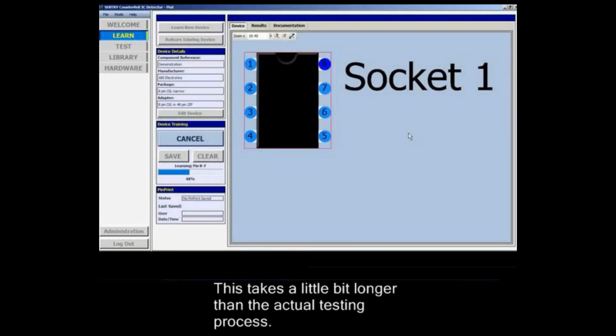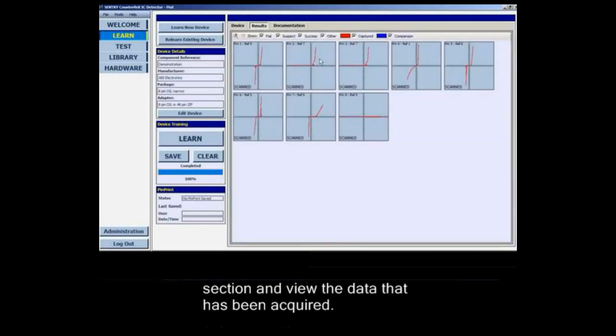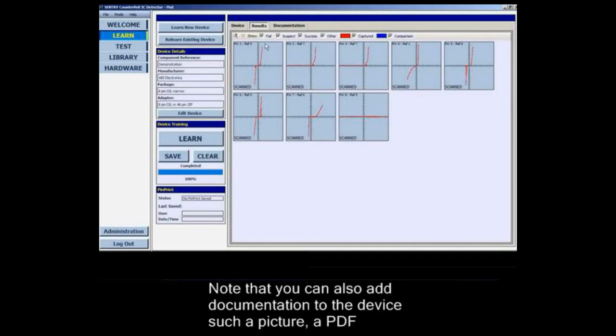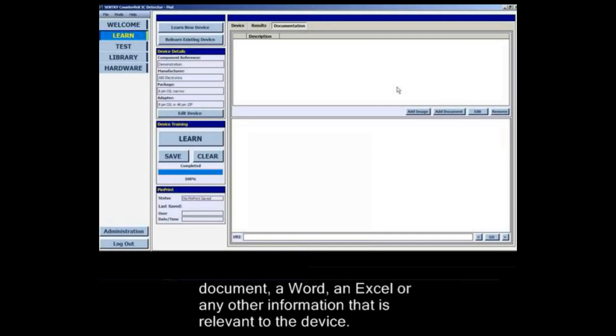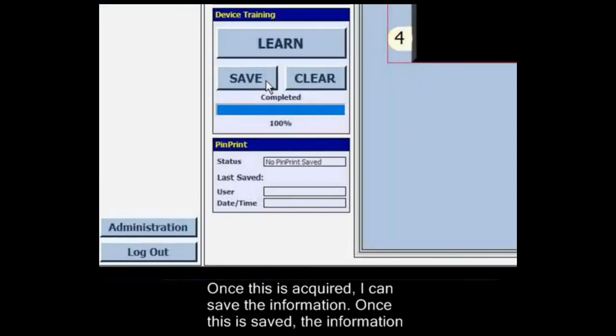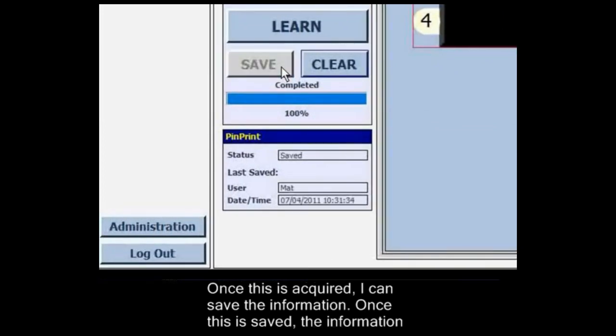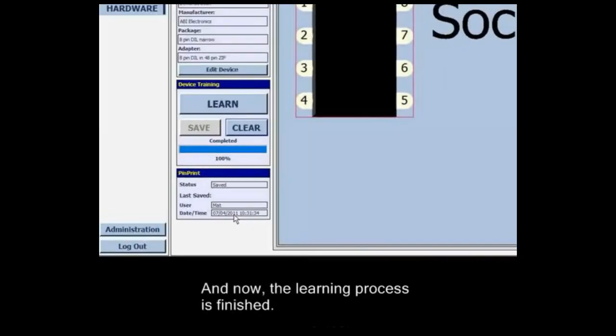This takes a little bit longer than the actual testing process. Once acquisition is complete I can go and look at the pin prints in the results section and view the data that has been acquired. Note that you can also add documentation to the device such as a picture, a PDF document, a Word document, an Excel file, or any other information that is relevant to the device. Once this is saved, the information including the user, date and time are saved against this particular device, and the learning process is finished.